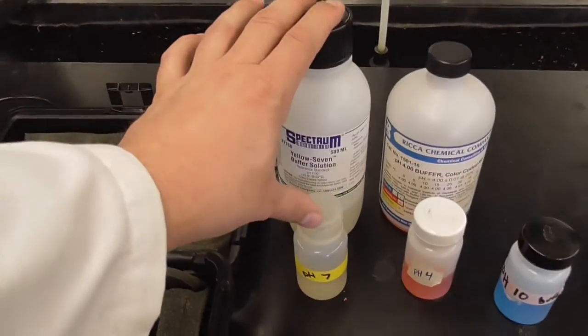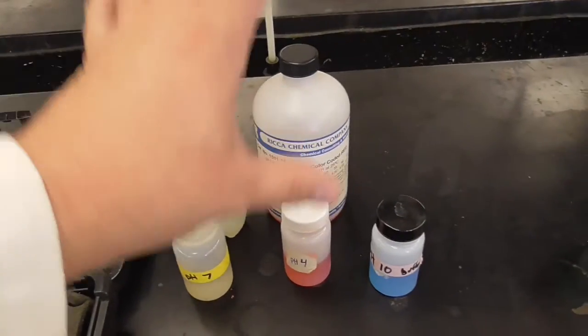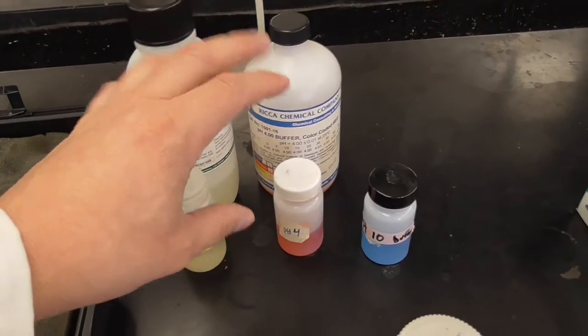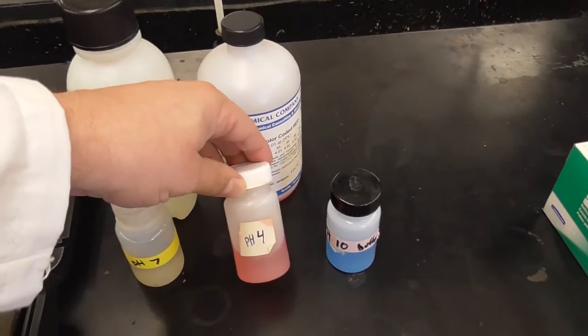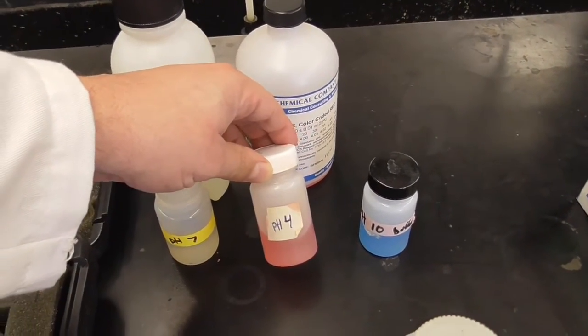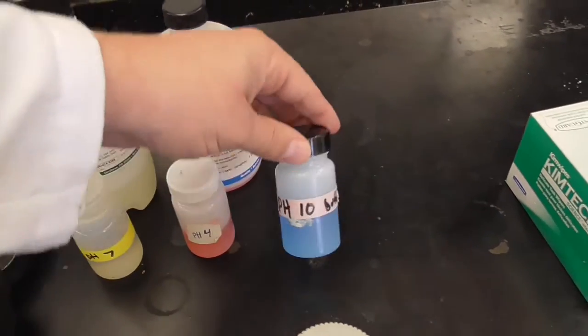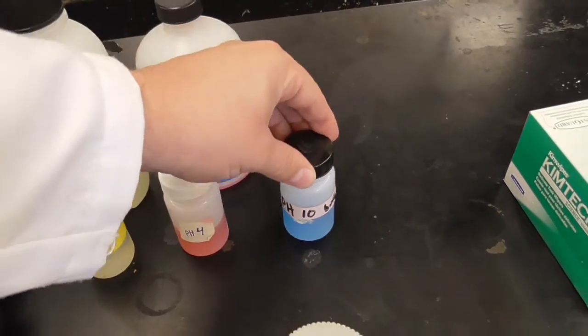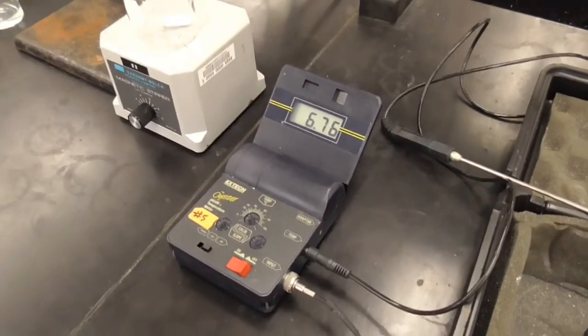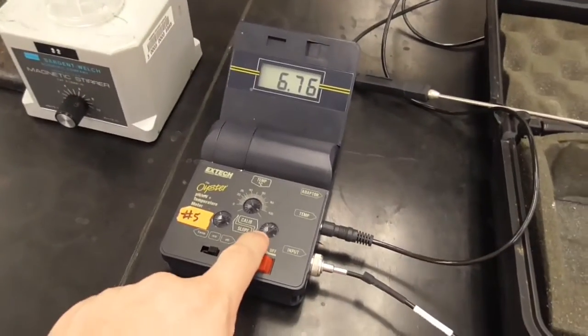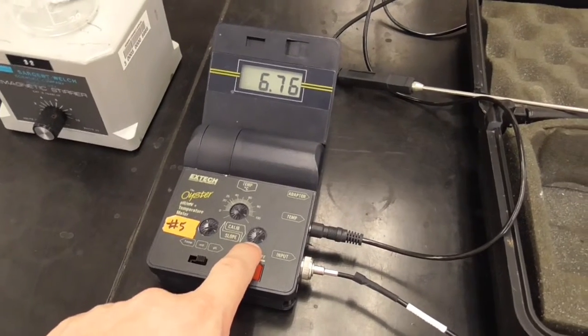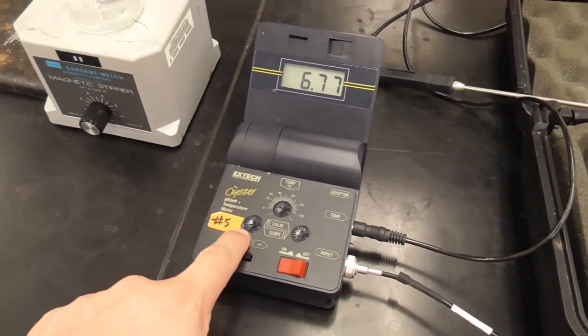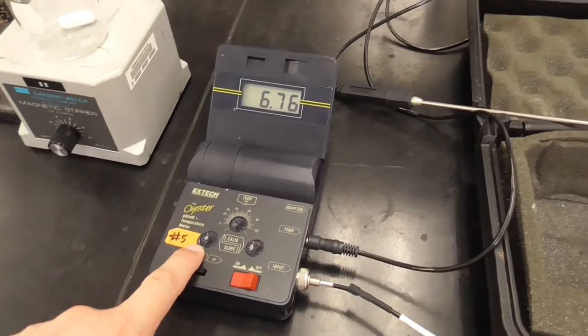You need this pH 7 buffer. You also need a second buffer, okay? Now, we have a couple of choices. We have a pH 4 buffer, which is red, and we have a pH 10 buffer, which is blue. So this type of pH meter has a 2-point calibration. You calibrate, use the calibration button for the pH 7 buffer and the slope button for your other buffer.